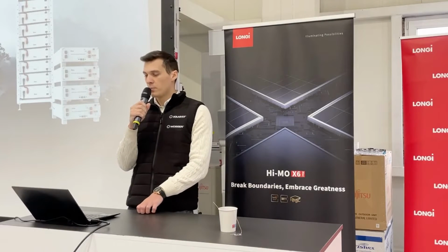This inverter is quite a unique one because of the power ranges and the low voltage battery it uses. Also, it has a load port and a generator port. The generator port has a lot of functions. You can add a generator, as the name suggests, but you can also switch this port and use it as a smart load output. So from an input it becomes an output, and you can set parameters for a consumer on this port, so it will only consume energy when it's within the parameters you set in advance, letting you benefit more from the power you've generated.